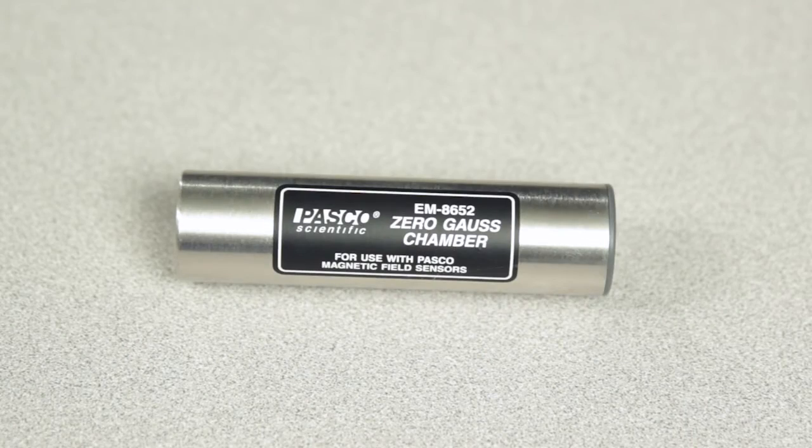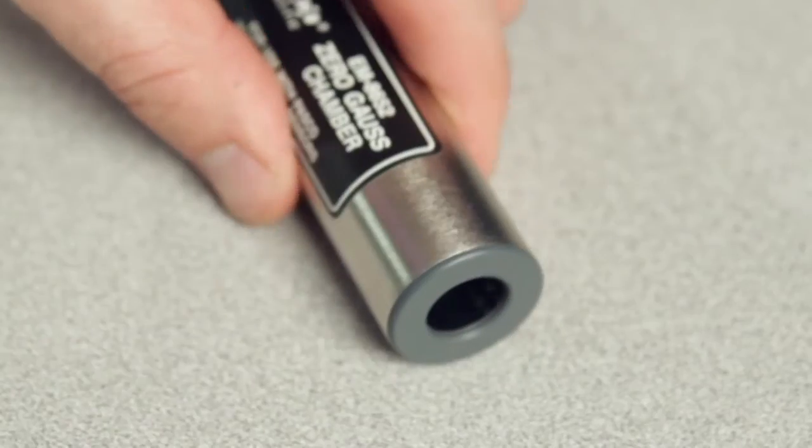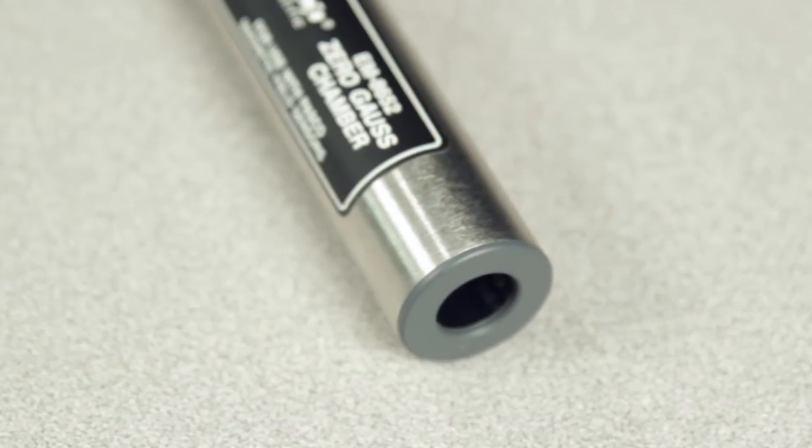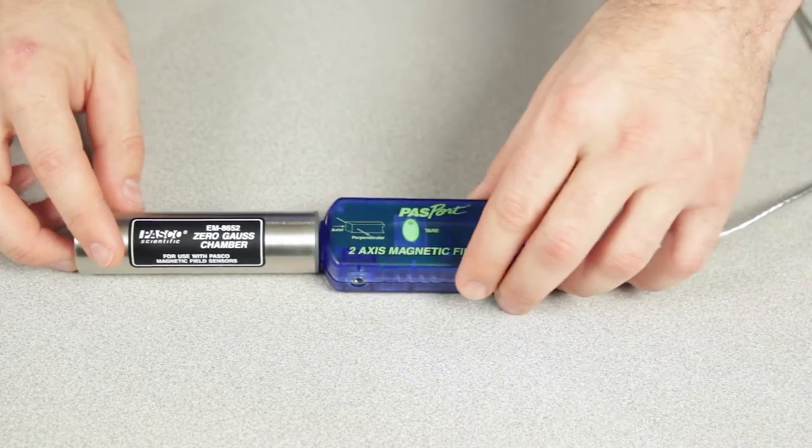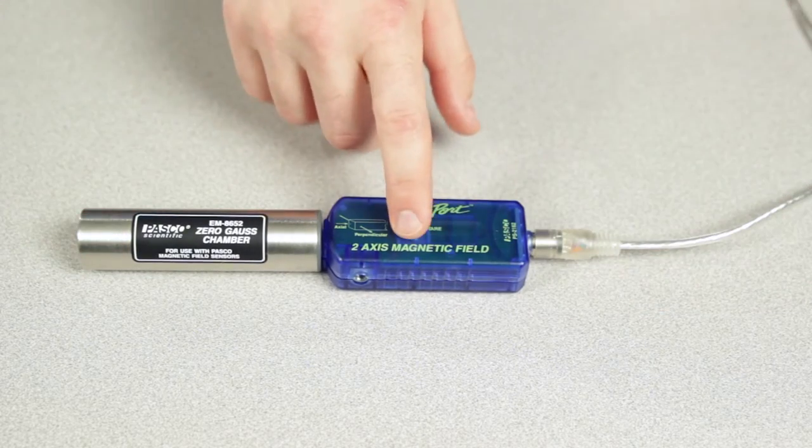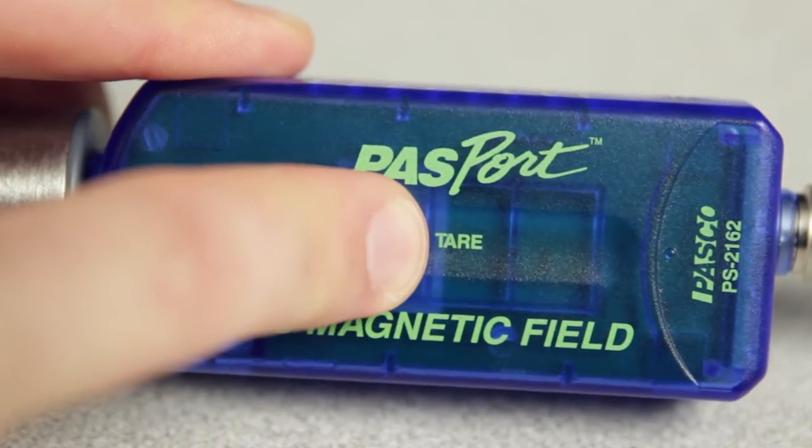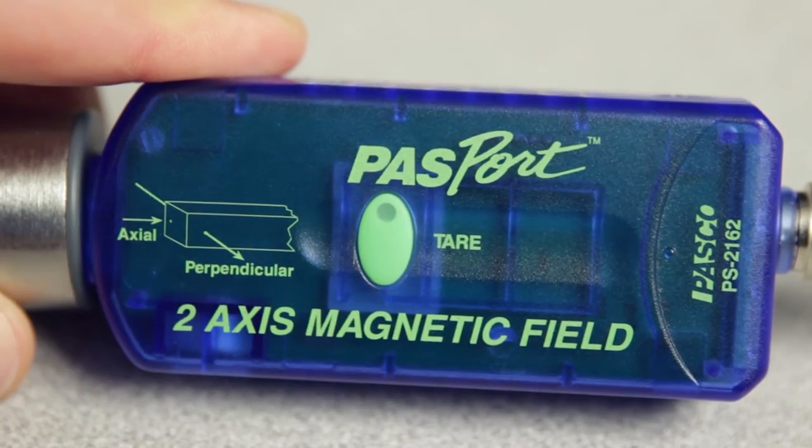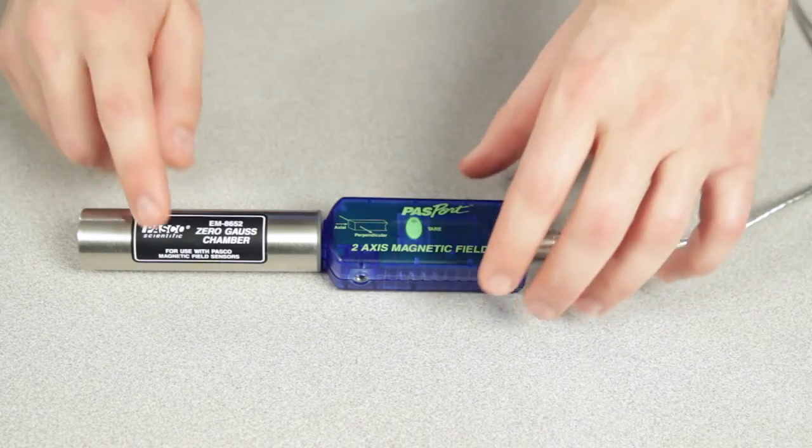Not included with the sensor is the optional 0 Gauss chamber that can be used in conjunction with the sensor's tare function. The double-walled high permeability metal chamber produces a 0 Gauss field within it. By placing the magnetic field sensor probe into the chamber and pushing the tare button, the measured magnetic field strength value can be reset to 0.